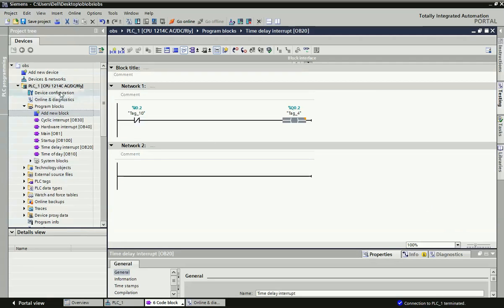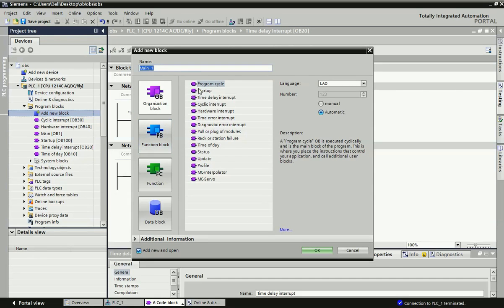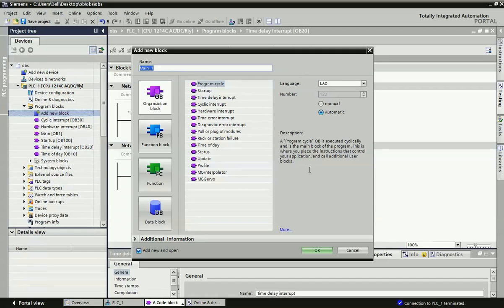We are now in Siemens TIA Portal software. I have configured a Siemens S7-1200 series PLC. These are the different organization blocks used for different applications and events. From Program Blocks > Add New Block you can get the full list of different OBs. The Program Cycle OB is like the main OB where you place instructions to control your application — it is a general purpose programming block. The Startup OB executes only once when the PLC changes state from Stop to Run mode.